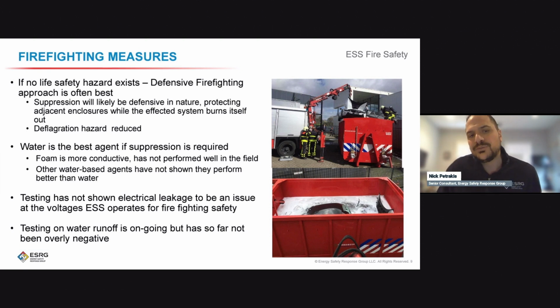Our emergency response procedures are very defensive. These systems are designed to either contain that failure, or if it becomes larger, safely consume itself. On the fire department end, you can be very defensive—you can limit the amount of water, and just let it safely consume itself. When you do that, we don't have to worry tremendously about water intrusion or leakage, because water is really not used unless it's to cool or wet the perimeter within the facility.